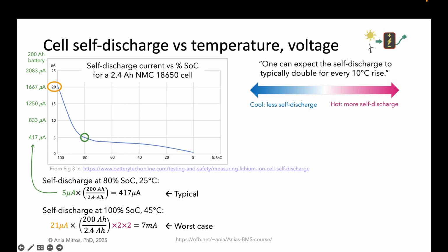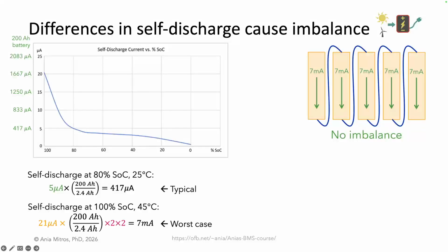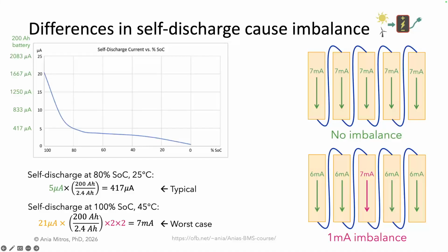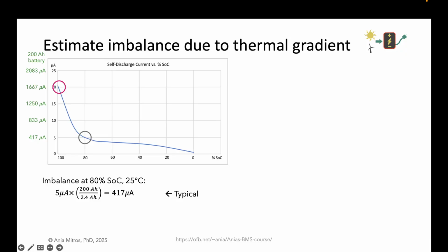Our worst case corner is at 100% state of charge and hot, say 45C, where we estimate the self-discharge to be about 7 milliamps. With regards to imbalance, what matters are differences in self-discharge, not the absolute value. For example, even with the worst case self-discharge, if all the cells are self-discharging equally, they will remain balanced. Imbalance comes from unequal self-discharge. For example, if one cell is self-discharging at 7 milliamps, while the rest are self-discharging at 6 milliamps, the pack is accruing 1 milliamp of imbalance. To estimate imbalance, then, we need to estimate the difference between the cells with the highest and lowest self-discharge rates.